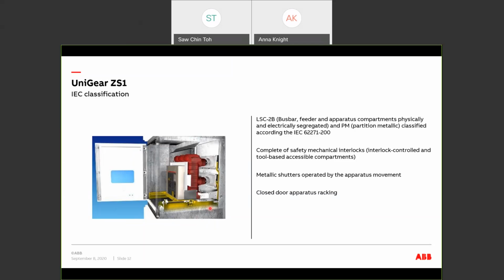Let's have a look at the circuit breaker compartment. It is designed in such a way that you can rack the breakers in and out and switch the breakers on and off with the door closed. This is an interlock controlled compartment. You can only open the front door of this circuit breaker compartment when the circuit breaker is racked out from the service position to the test position.